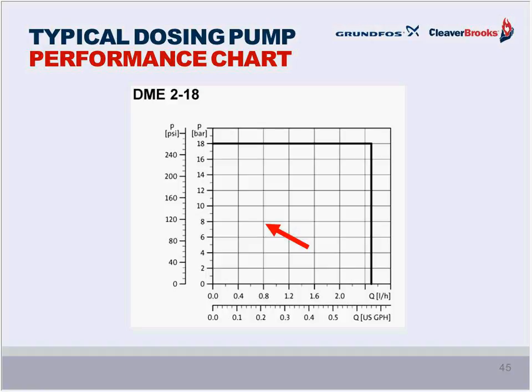When we think of the two main selection criteria of any pump, we talk about pressure and flow. This is an exciting view of the dosing pump performance chart, kind of sarcastically, because it's just a square. So the pump can operate on the lines and anywhere below and to the left of them. This is significantly different from the centrifugal pump curves that were in the previous webinars that we had with Grundfos. When we talk about metering pumps, the curve or chart is not as important as the maximum and minimum limits. So the maximum flow, the minimum flow, the maximum pressure, things like that. So we don't ask to see curves, but instead we look at tables that show maximum and minimum performance.